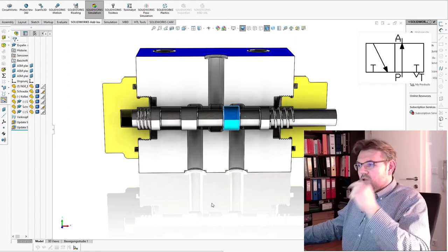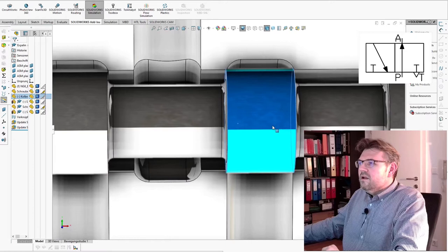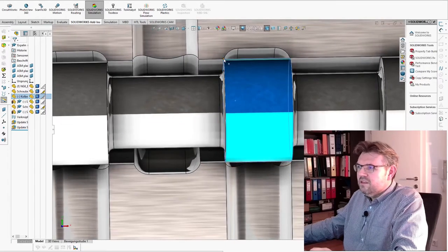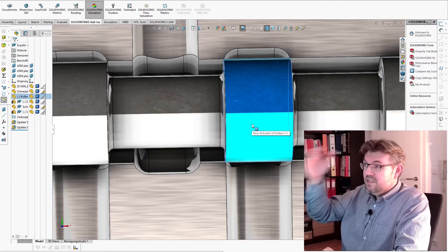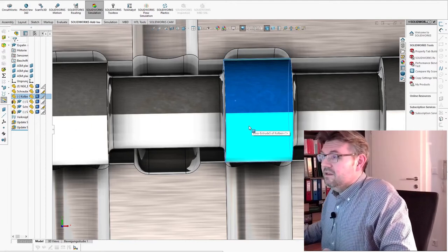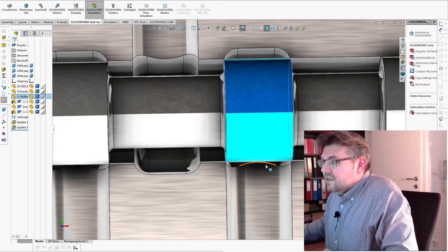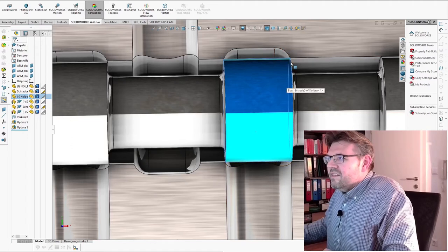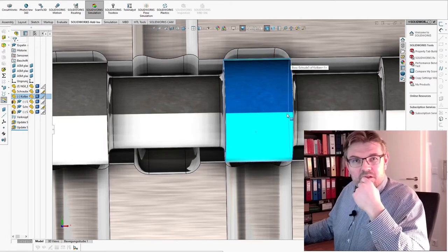So take a look at the piston. Yeah? This one here fits perfect into this broader area. This is zero overlapping. Zero overlapping piston. As soon as this is closing, everything is closed. However, this sealing interface is very, very tiny, so there is quite a lot of leakage.